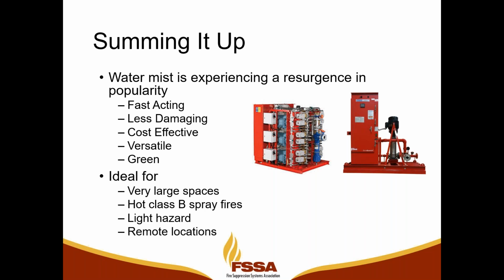Water has been used to protect light hazards since the mid 1800s when sprinkler systems first came out, and water mist is a step beyond a sprinkler in terms of its effectiveness. And then we've got remote locations where you need a self-contained unit that might have its own nitrogen source to power the unit and its own water supply. So hopefully that gives you an idea of why we've experienced this rapid growth in recent years. And next slide.